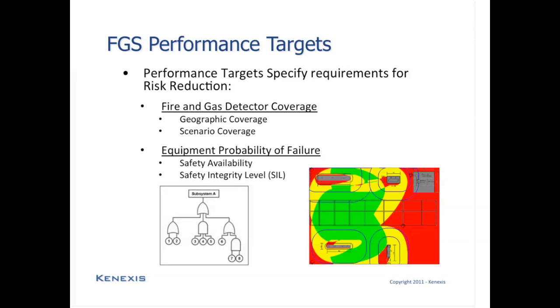So more precision was required on the lower end of the SIL spectrum. So it was determined that safety availability would be a more appropriate target, where a lot of the semi-quantitative approaches would have SIL targets for different fire and gas functions being low SIL 1 to high SIL 1 as opposed to SIL 1, 2, or 3. Even achievement of a SIL 2 for a single fire and gas system loop is going to make the probability of failure component of the overall risk so imperceptibly low in relation to all of the other risk factors that trying to achieve even better performance for the probability of failure is essentially a waste of resources because it's insignificant in the overall scheme of the risk.